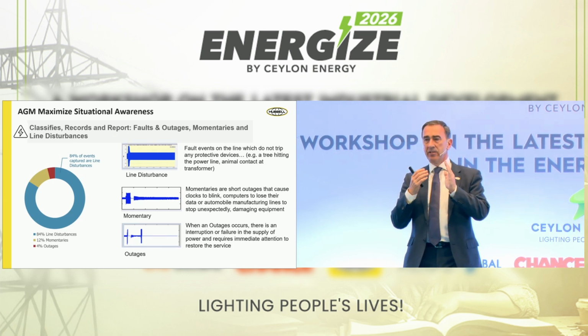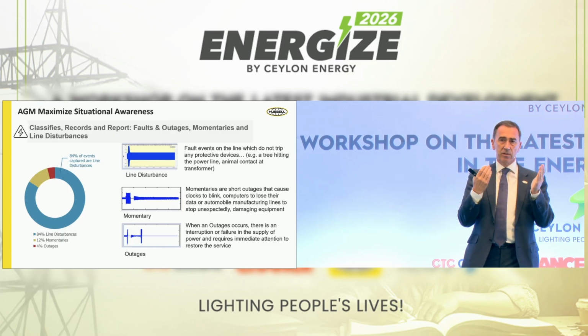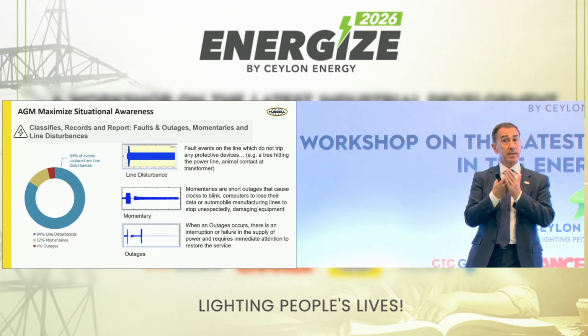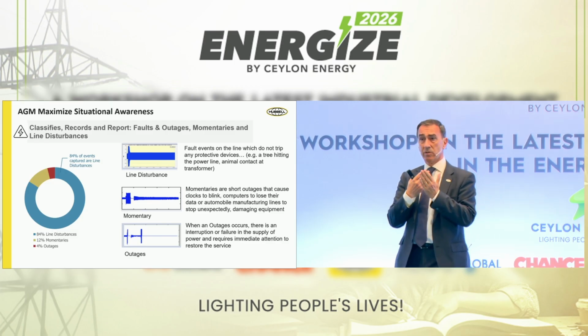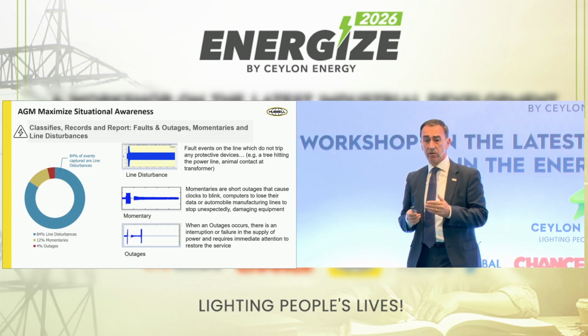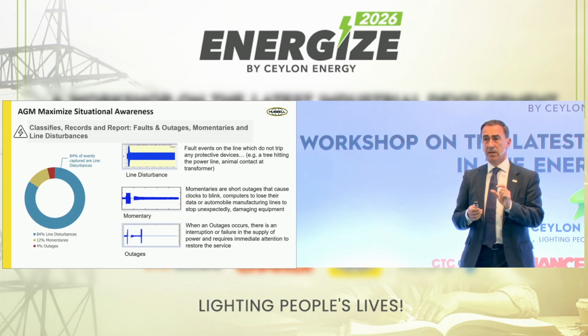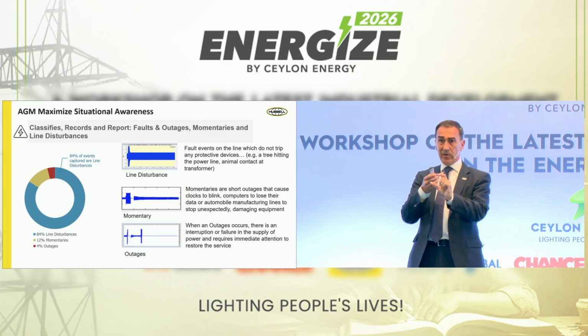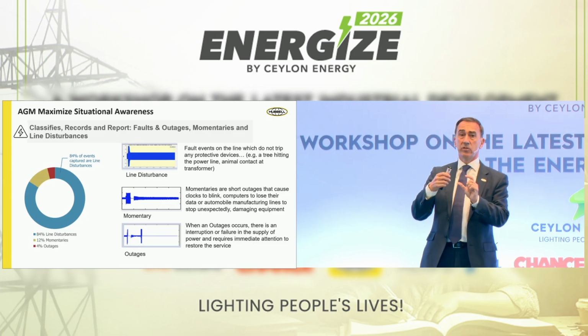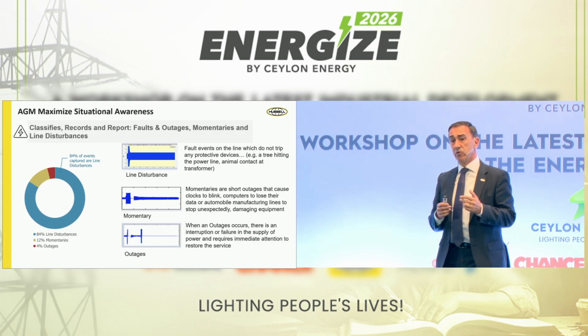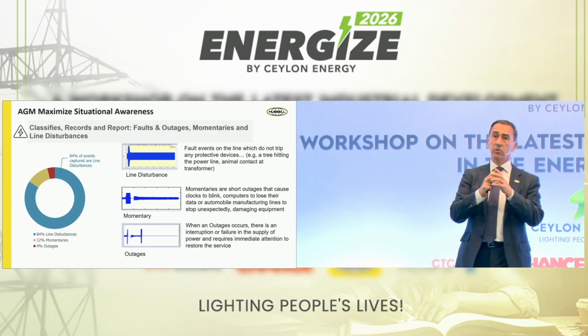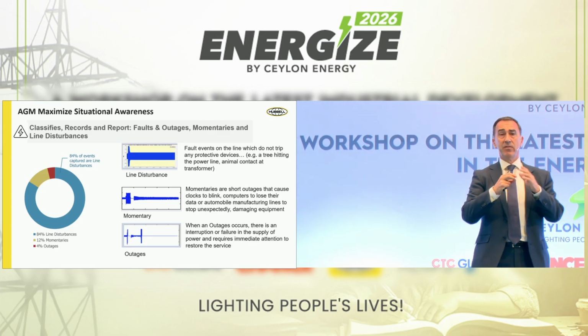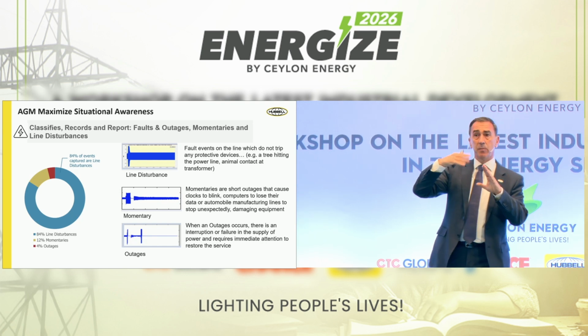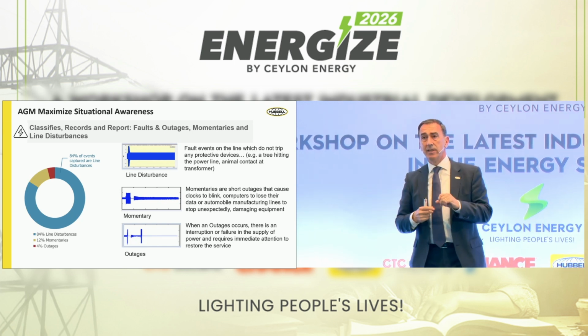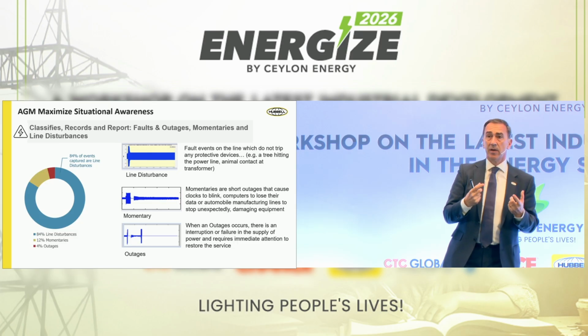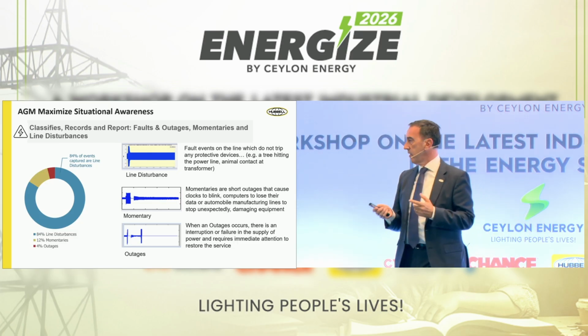For instance, a tree touching a line - it's not a fault, the meter won't disconnect, but something is happening. This will get worse and worse, and eventually you'll have an outage, a fault. Only 4% are outages, but most of these started with some kind of disturbance. So these devices are able to identify those disturbances early enough - they recognize the pattern and identify the issue, so you can go there and fix it.